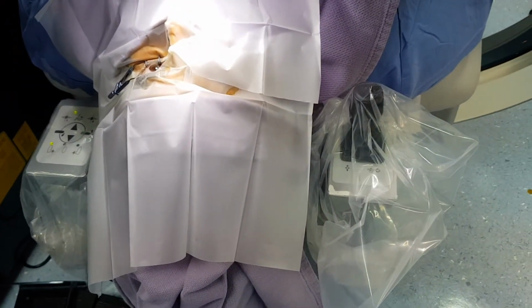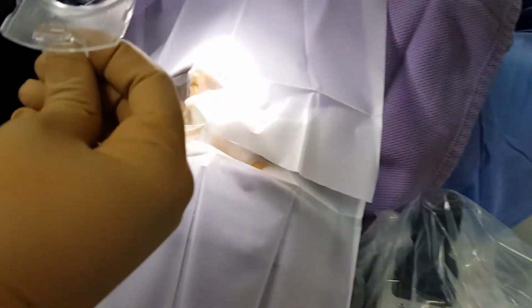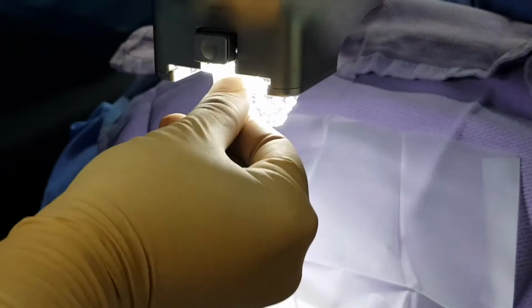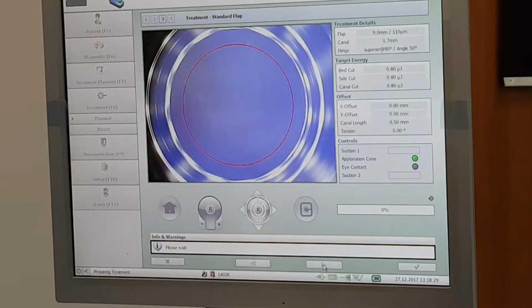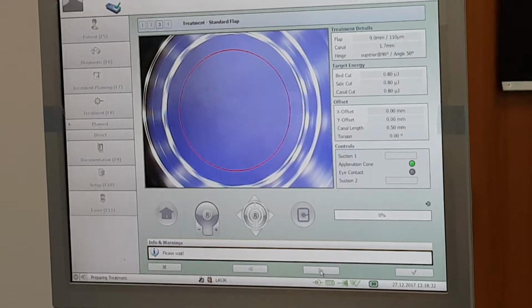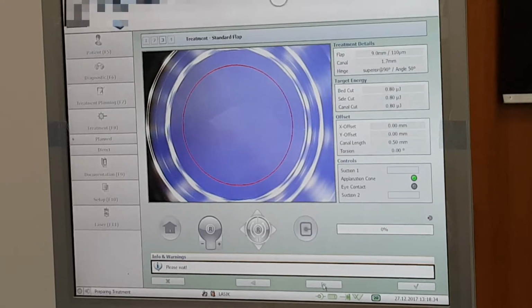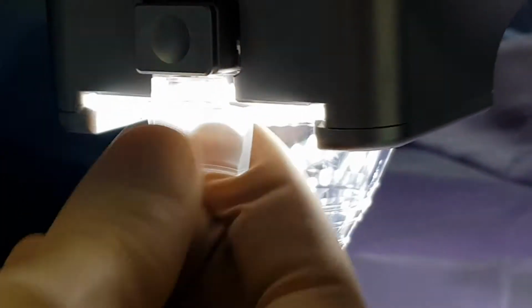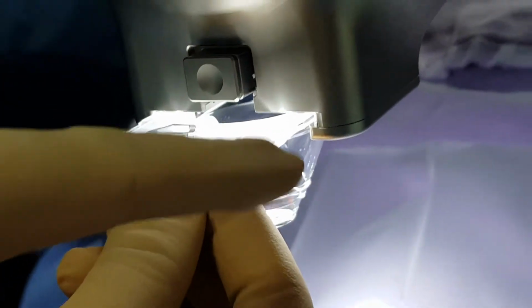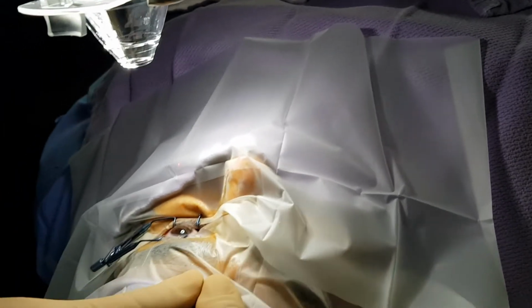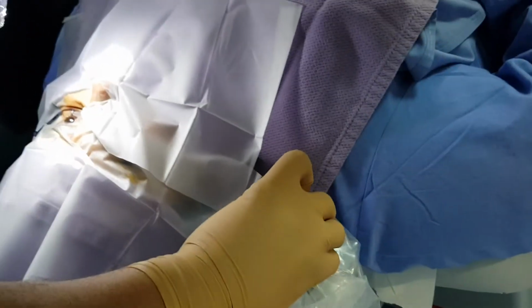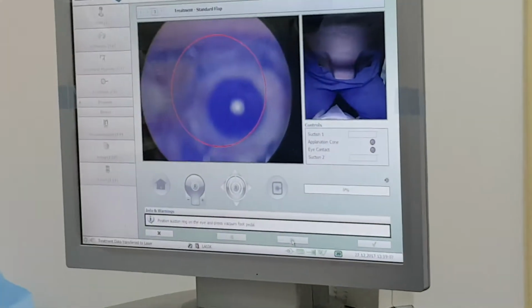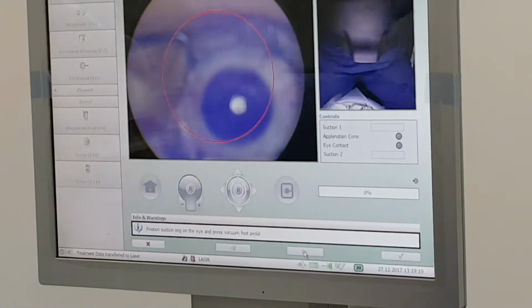We start the procedure by inserting the applanation cone for calibration, since each applanation cone is individually calibrated to adjust for variant in glass thickness. Once the applanation cone is calibrated, remove it to the parking position partially. Adjust the patient head by rotation opposite to the treated eye, then use the bed's joystick to center the eye and have the two red dots intersect, then move further to the limbus.